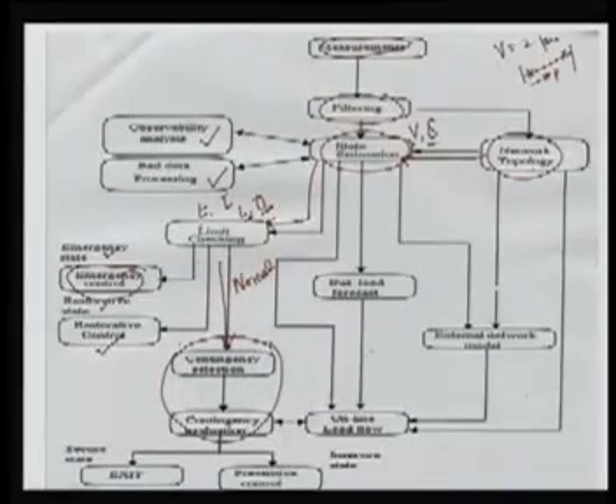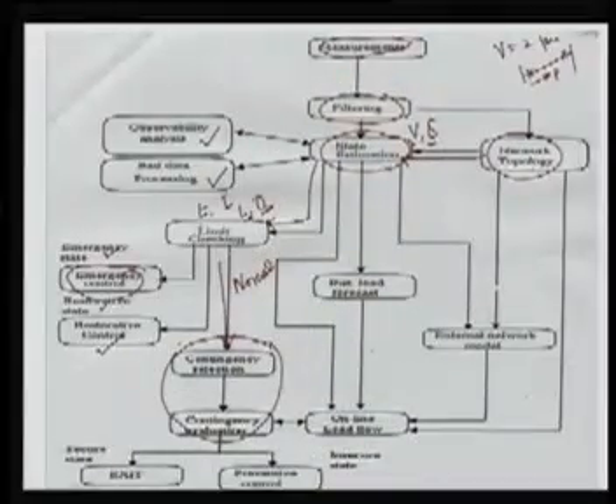So it is very important that the security analysis or contingency block, this block is called the contingency or security analysis, is only performed if your present operating system is in the normal state. Otherwise, if it is not in the normal state, then we have to take corrective action or preventive corrective action so that we can bring your power system into the normal state. Now you can also see this. Now in contingency analysis, we require several other pieces of information.